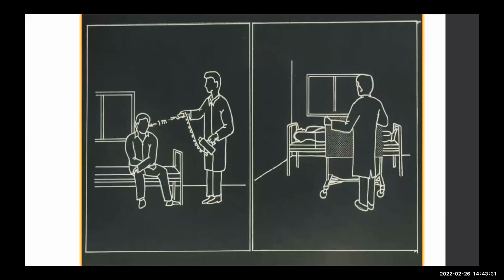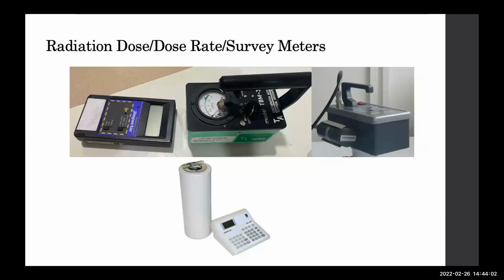Now, this is very familiar to you. When the patient is administered radioiodine and admitted in the isolation ward, then after administration of the oral dose of radioactive iodine, you measure the dose from the organ of interest, that is the thyroid. It is the survey meter, which is an ion chamber based survey meter, which is used for measuring the dose or dose rate from the organ of interest, and at the time of discharge, whether the radioactivity has fallen below the permissible level is measured. This is a very familiar instrument to all of you.